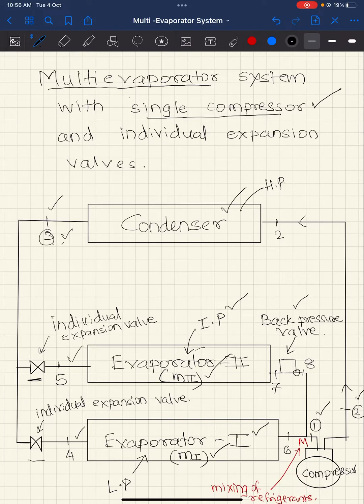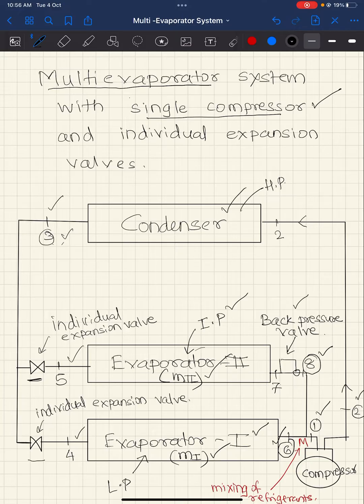To bring the refrigerant from intermediate pressure to the suction pressure, we employ a back pressure valve. It expands the refrigerant from state 7 to state 8, which is a throttling process. At state 8, the pressure becomes equal to the pressure at state 6 — both are now at the lowest pressure in the system. Because the refrigerant at state 8 and at state 6 are at the lowest pressure, they can be mixed at point M, and the mixed refrigerant enters the compressor at the lowest pressure.